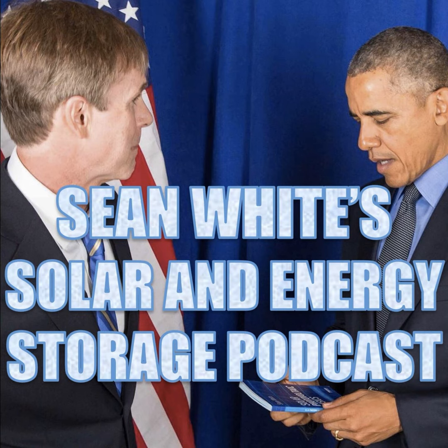And then we go back to our Chapter 7, Energy Storage Systems. Back at Disconnecting Means, we're talking readily accessible. So also this disconnecting means, or a lot of times we call it a disconnect or a disco, if you like 70s terminology. So just what we're saying here, and we're going to call this 706.15(A)(2), is we want it to be in sight, but if it's not practical to put it in sight, put it as close as you can.